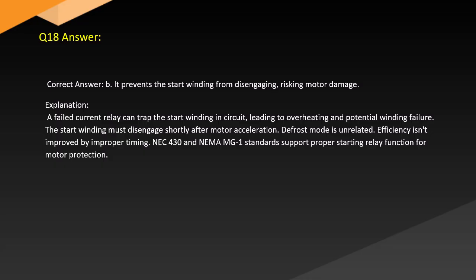Answer. Correct answer: B. It prevents the start winding from disengaging, risking motor damage. Explanation. A failed current relay can trap the start winding in circuit, leading to overheating and potential winding failure. The start winding must disengage shortly after motor acceleration. Defrost mode is unrelated. Efficiency isn't improved by improper timing. NEC 430 and NEMA MG1 standards support proper starting function for motor protection.